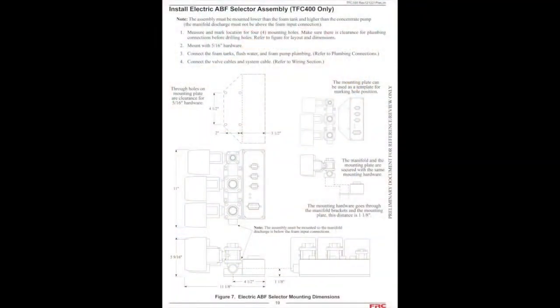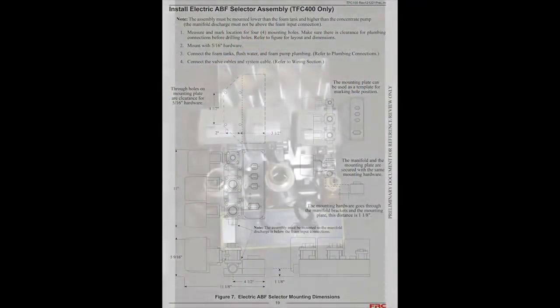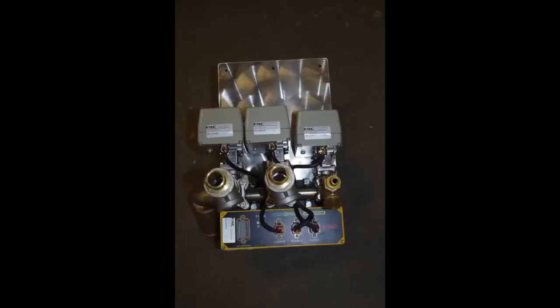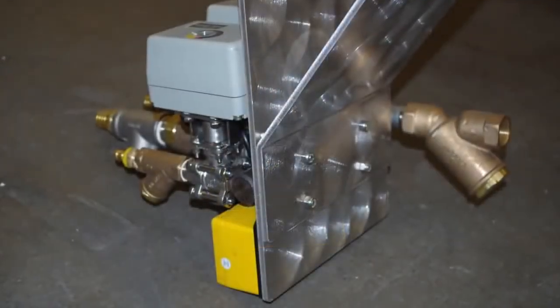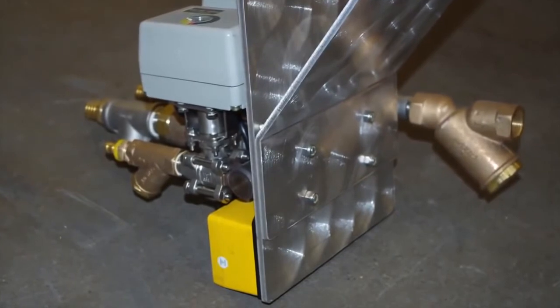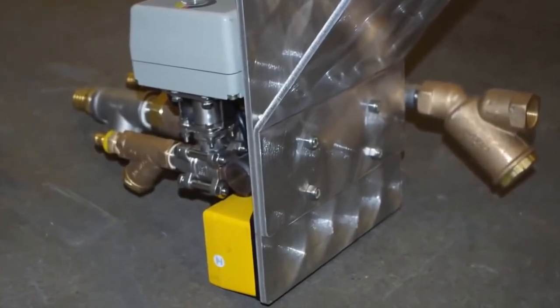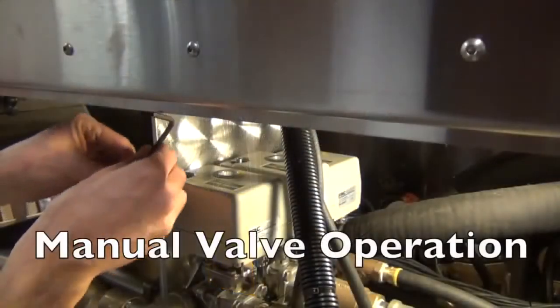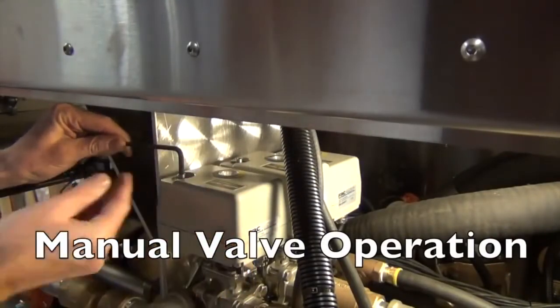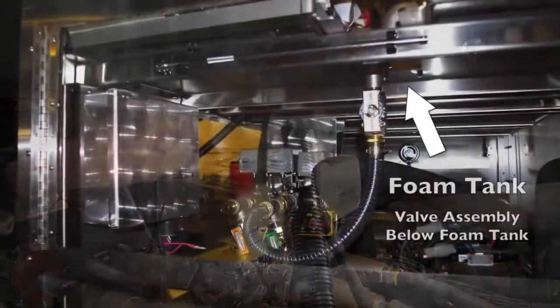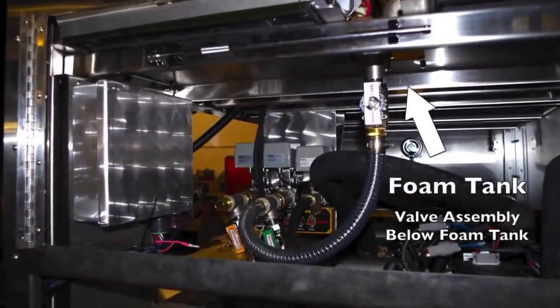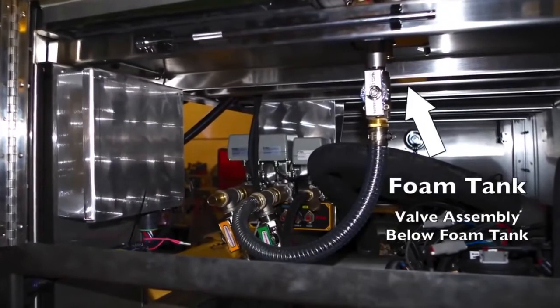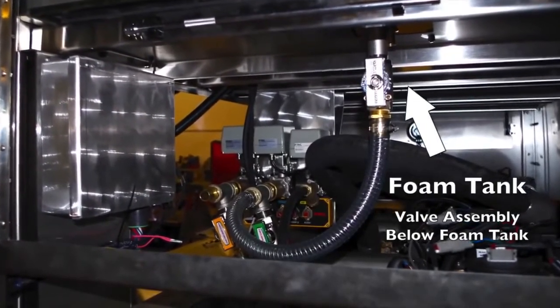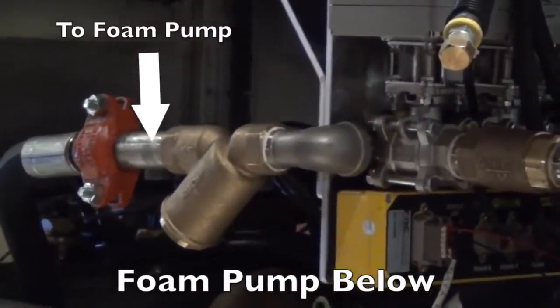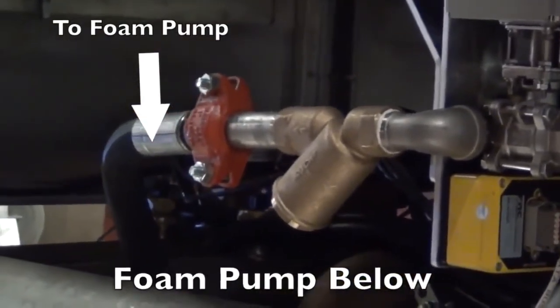We will now go over the electric ABF selector assembly installation and plumbing. The electric ABF selector assembly is attached with 4 5/16" bolts. When mounting, leave room to access the valve for manual operation as well as all plumbing connections. The electric ABF or any manual selector assembly must be located lower than the foam tanks. The foam pump must be below any selector valve assembly.